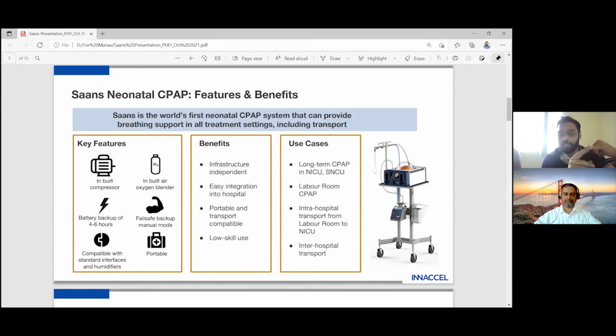So it has firstly an inbuilt compressor. So therefore you don't require an external compressed air line. It has inbuilt air oxygen blending, and it is compatible with a range of oxygen sources. So if there is a central oxygen line, that will work. Otherwise cylinders will work. We've even tested it now with oxygen concentrators. It has a built-in battery backup.